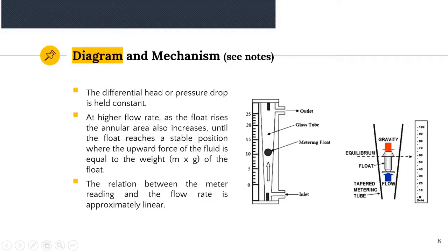You read it at the float's highest point and largest surface area. If the float is spherical like this, then it's the middle of the sphere, so it's around 11.